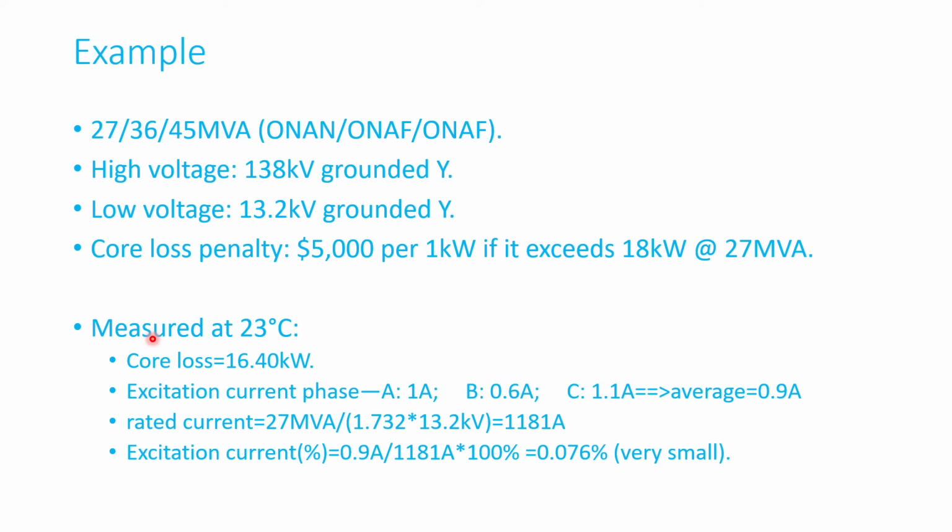During the core loss test, the temperature was 23 degrees Celsius. Core losses were measured at 16.4 kilowatt.